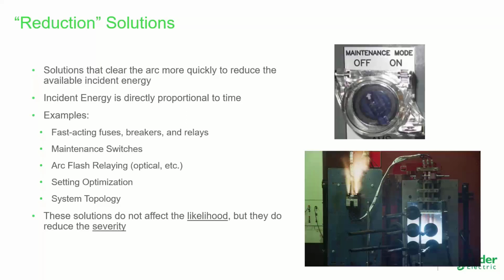Sometimes reducing arc flash levels is as simple as making sure we correctly consider arc flash incident energy levels when we're doing coordination studies. That's what I mean by setting optimization. I continue to be surprised how many times I see studies that have been done either by colleagues or by others in the industry where really it seems apparent that the folks doing the study really don't understand the full capabilities of the protective relays or other devices that they're dealing with, and are just missing an opportunity, almost a free opportunity, to reduce incident energy in their system. So it's very important to perform the correct kind of studies and optimize those settings.